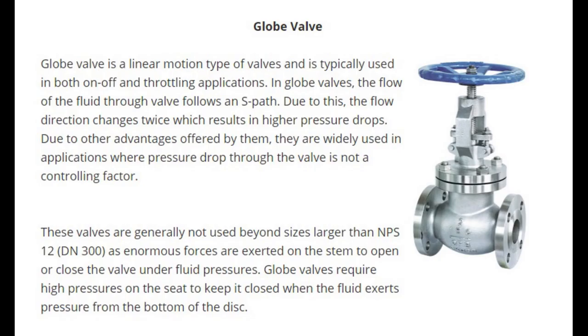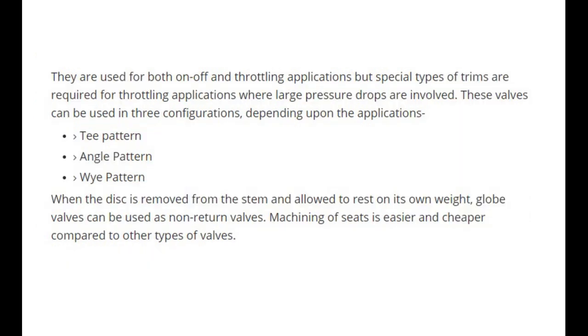Globe valve is a linear motion type of valve typically used in both on-off and throttling applications. In globe valves, the flow follows an S-path, so the flow direction changes twice, resulting in higher pressure drops. Due to other advantages, they are widely used where pressure drop is not a controlling factor. They are generally not used beyond NPS 12 (DN 300), as enormous forces are exerted on the stem to open or close the valve under fluid pressures. Special types of trims are required for throttling applications where large pressure drops are involved.